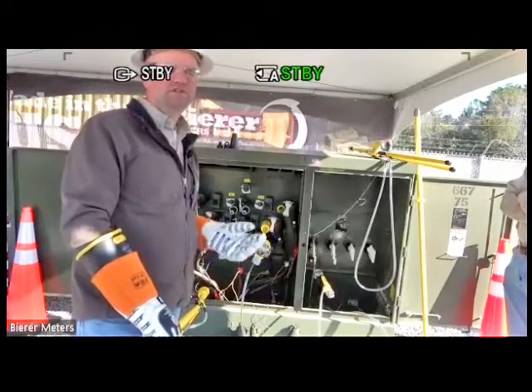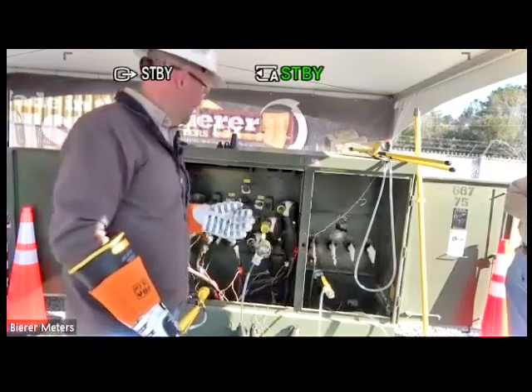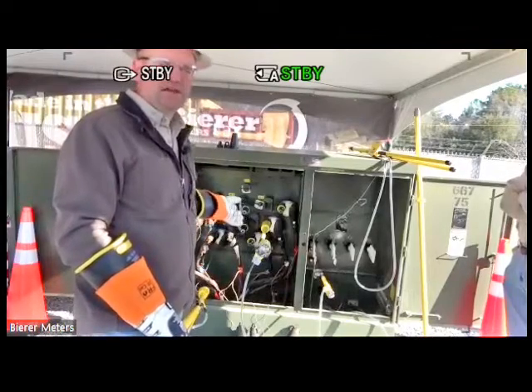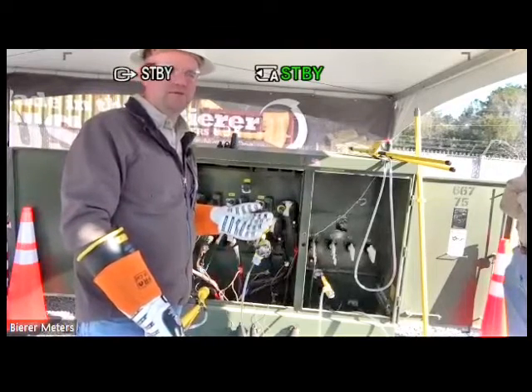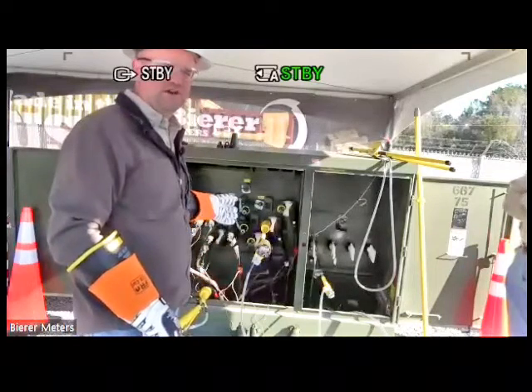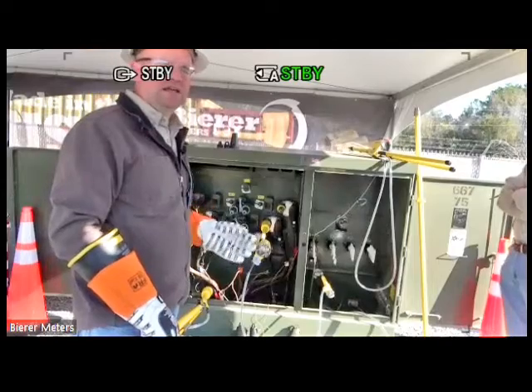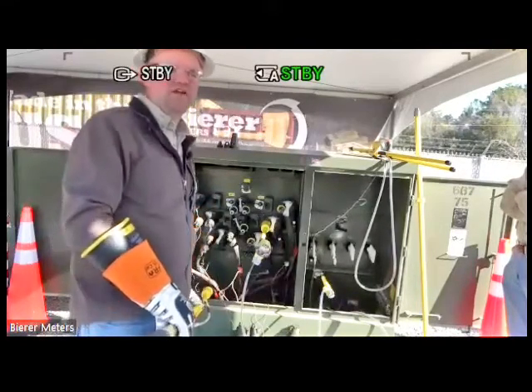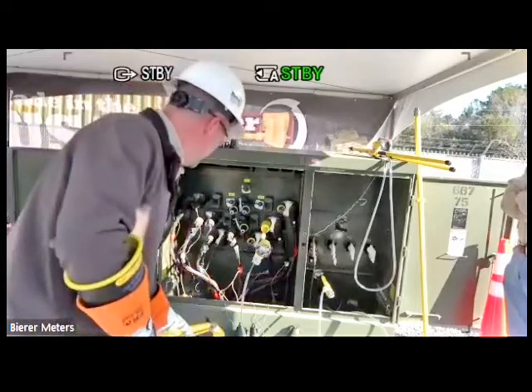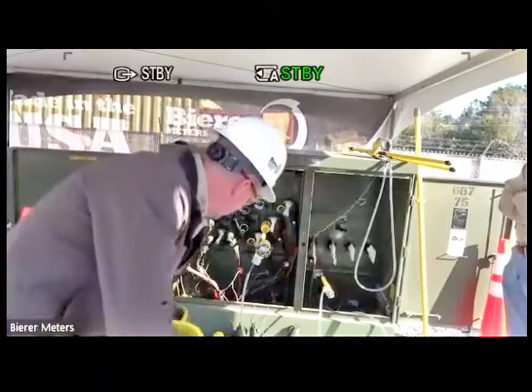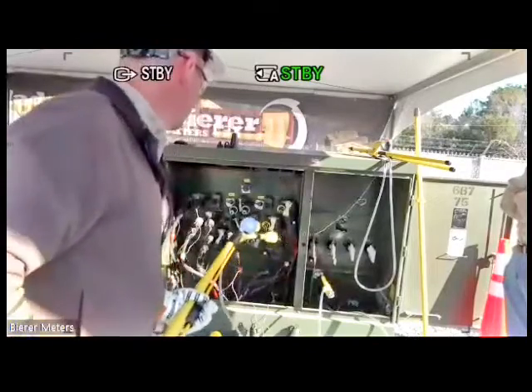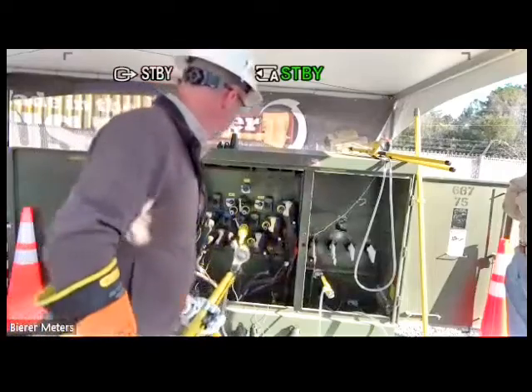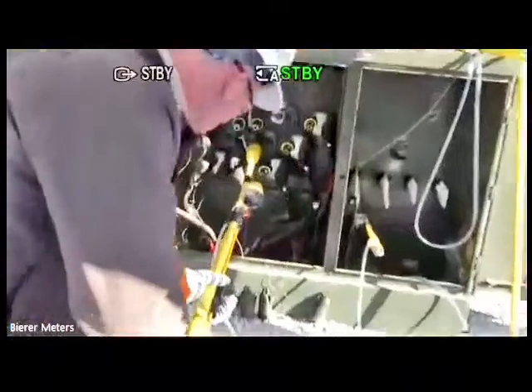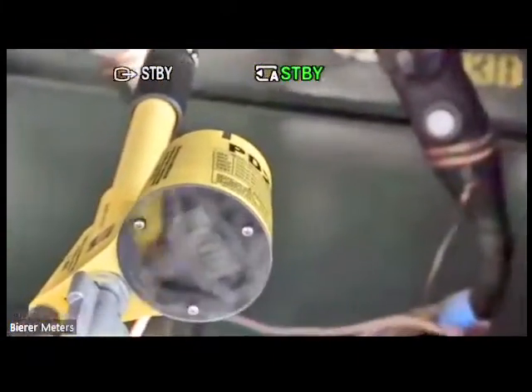So it's essentially one of three scenarios whenever you're using this tool as a high pot adapter or a high potting meter: you'll see a low number representing a good cable, a constant high number representing a bad cable, and then maybe a high impedance fault, somewhat like what I was trying to duplicate just a moment ago. And again, that's still a bad cable. So those are the three scenarios that you'll come across. So again, we want to discharge this cable. So I want to take my high pot adapter back to my source, which is the cable we just energized. And then I want to take my second probe and make sure I attach that to ground again. To de-energize, I can watch that scale. I see it jump up a little bit and go right back down to 0. Okay, so I know that's de-energized.